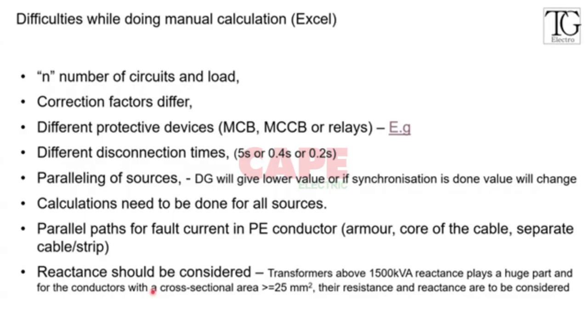If you ignore reactance and do a calculation, then in a circuit after a certain point in the main panel or in the sub main panel, if you check the fault loop impedance, it will be much higher compared to the designed value. That is due to this reason, because reactance is not considered.